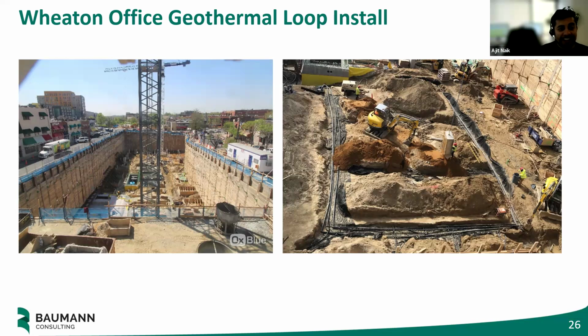I can give an example here. One of the tests required is a hydrostatic pressure test - after you dig all the holes, put in all your pipes and hook them up, before doing anything else, you fill them with water, pressurize it to 100 psi, and hold it for a while to make sure you don't lose anything. If you lose anything, that means you're leaking. On this project, the contractor - the driller or mechanical contractor - kept doing it and kept failing the test. They ultimately weren't reading the spec.